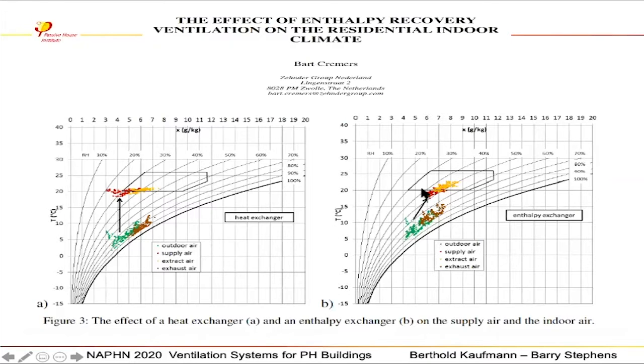With the ERV, you'll see those red dots indicating the incoming air, there's a little bit of a trade-off between an HRV and an ERV. The ERV has a little bit lower sensible effectiveness, so the incoming air temperature is a degree or two lower. But what you see is the relative humidity of that air is in the box. And so we're retaining humidity in the wintertime. We have a small penalty for sensible, or the incoming air temperature, but that's something you look at.